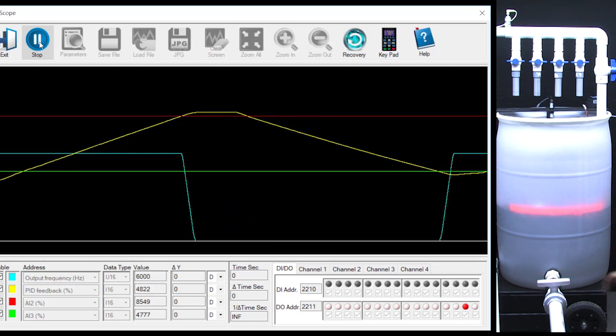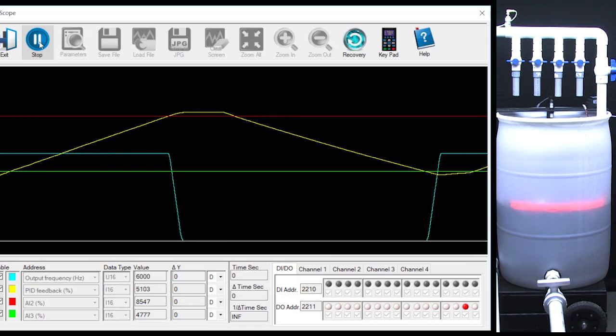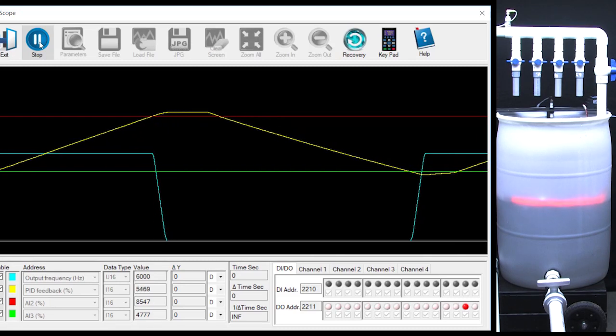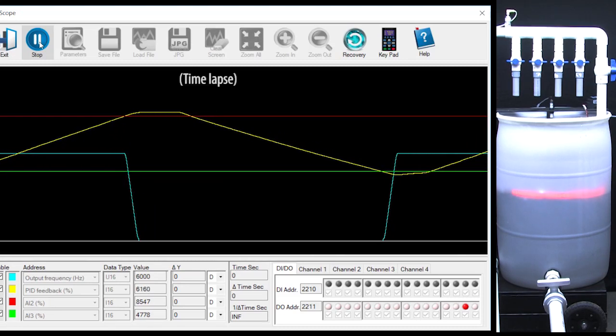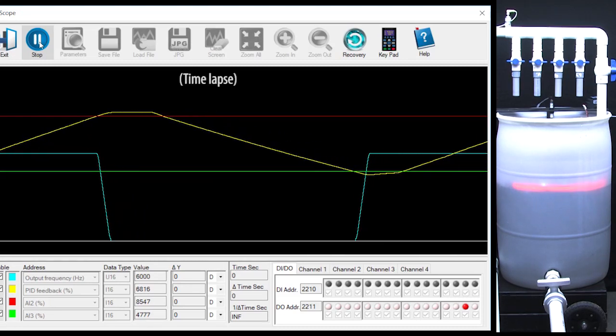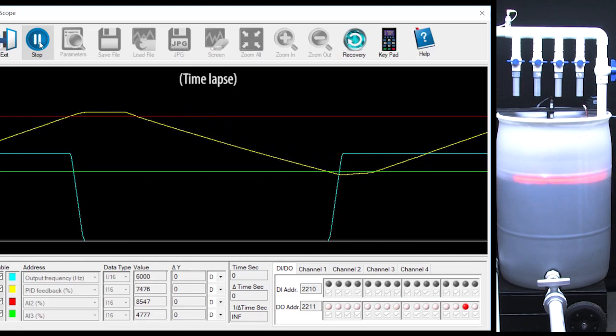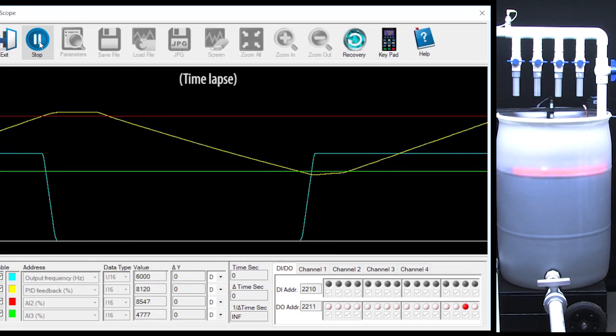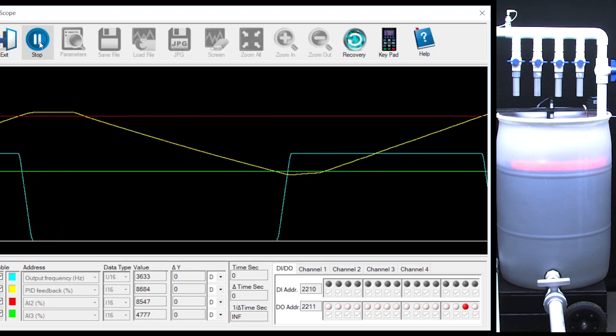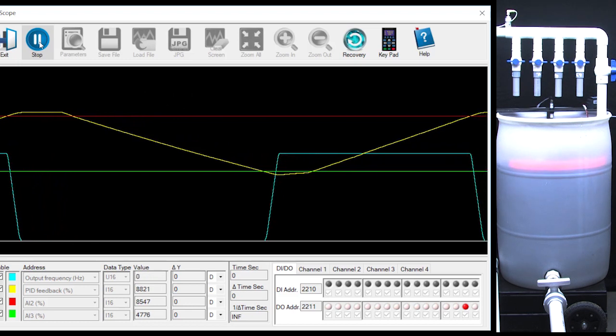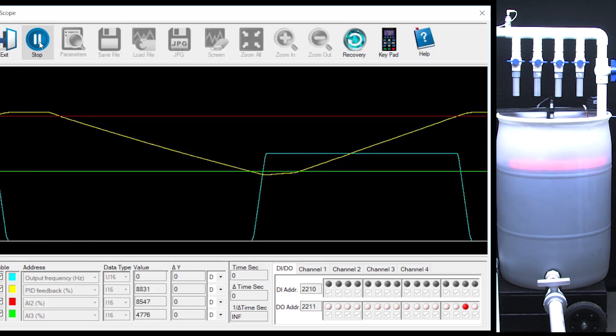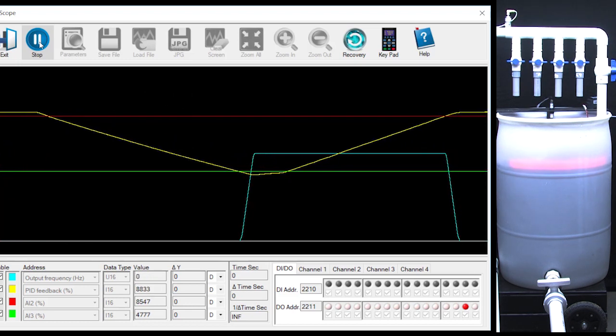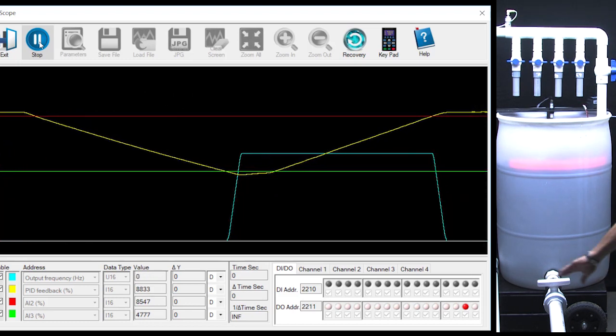I close the drain valve to speed things up a little bit. When sleep mode sees the yellow process variable or sensor feedback reach the sleep level it turns the output frequency off, which ramps down at the deceleration rate we set.